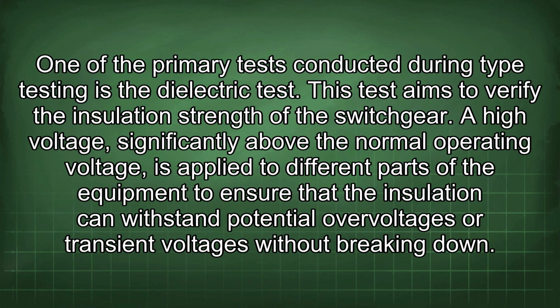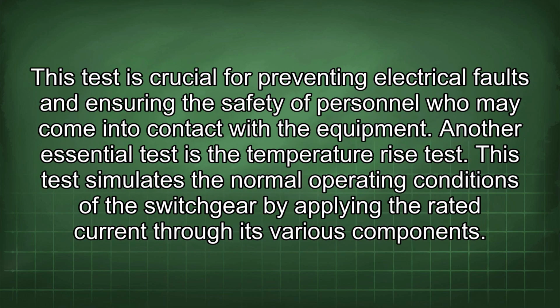One of the primary tests conducted during type testing is the dielectric test. This test aims to verify the insulation strength of the switchgear. A high voltage, significantly above the normal operating voltage, is applied to different parts of the equipment to ensure that the insulation can withstand potential overvoltages or transient voltages without breaking down.